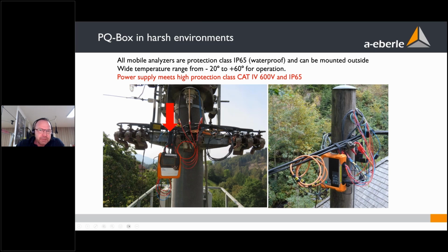Here's another application, a PQ-Box 200 installed on overhead cables. Here we have isolated cables. We use the currents with Rogowski, and we have here the connector to take the voltage and even the power supply directly from the cable, to measure in overhead lines over weeks outside in the field. If you measure outside, we also have big temperature changes. So we have to measure even at -20 and up to +60 degrees if the sunlight goes directly on the analyzer. So absolutely no problem.